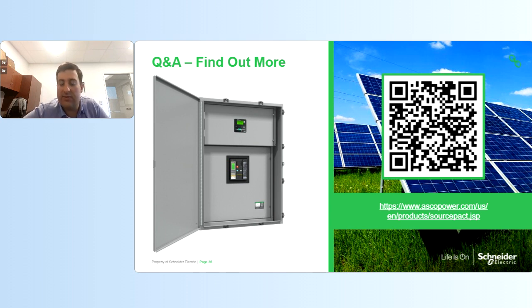However, when you want to go islanded mode, that would come down to the external microgrid controller that's doing the more high-level control of the entire system, rather than just providing the isolation function, which is what SourcePact does. And SourcePact could be the device that would open to give you the ability to run in almost a peak shaving mode or a demand response type application if you needed to. So I think that was addressing one of the questions.